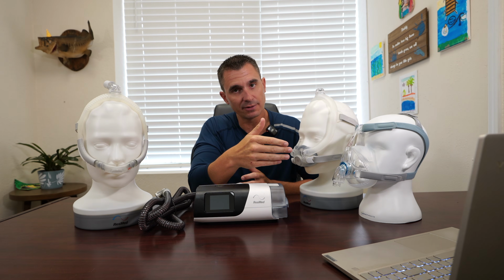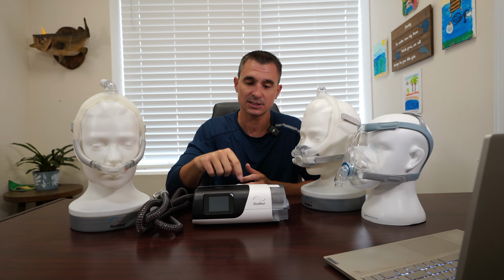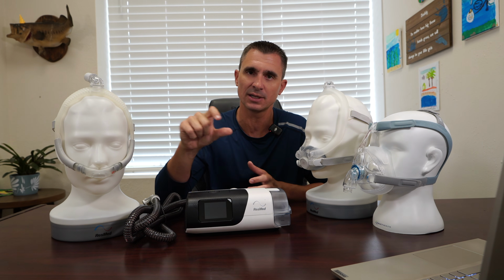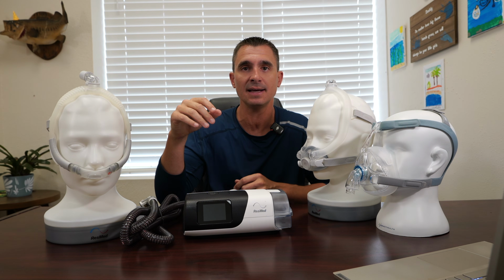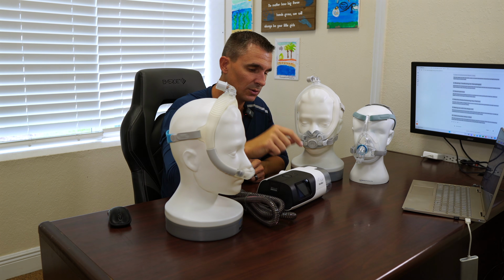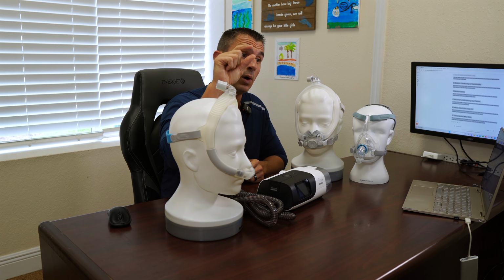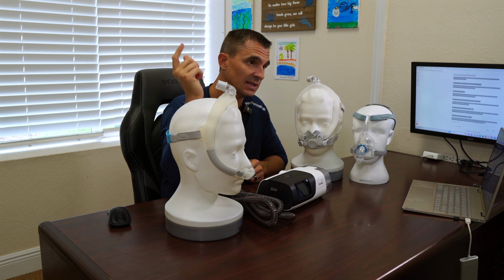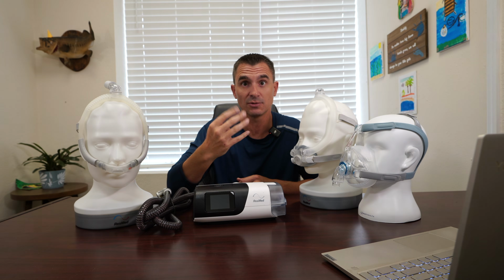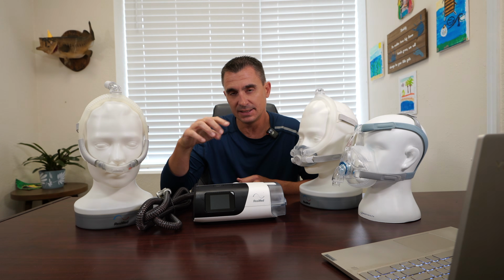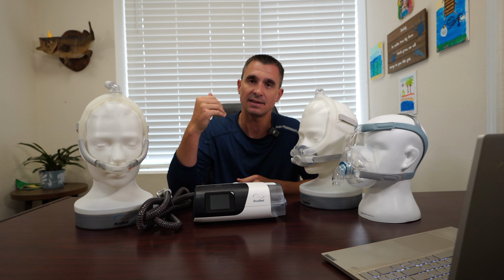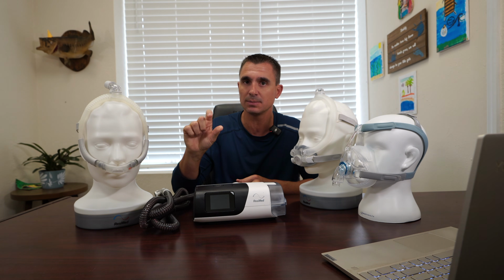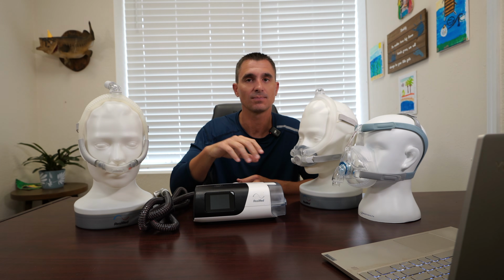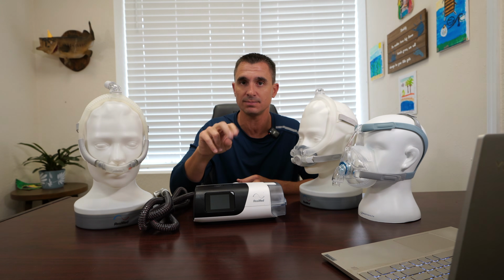Other times, if you're already on a full face and you've got a dried out mouth, you probably need some adjustment on the CPAP humidity setting. So a lot of these come stock to the customer with an auto setting. That can be really great for people. It'll turn humidity up and down as it can, but sometimes you just got to crank it up. So you'll go into your humidity settings, increase it one tick at a time. Don't go crazy, or the next thing you know, you'll be talking about issue number 4. But you just need to adjust it up slightly. Try to compensate for it. If you've got a heated tube, adjust your heated tube temperature up just a little bit as you adjust the humidity up. Those 2 solutions typically remedy this problem.